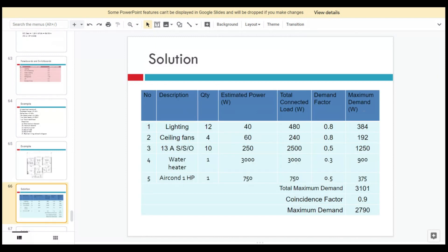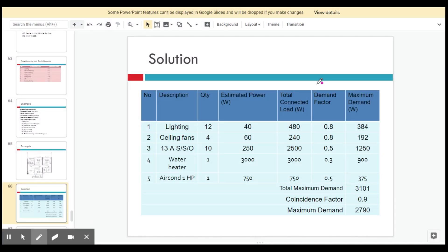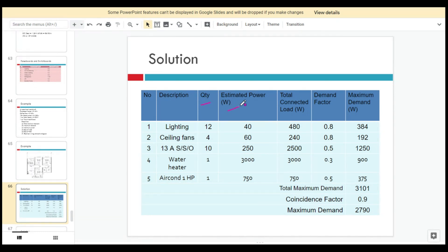From there, with one air conditioner, you have to come up with the load calculation. Load calculation is very important in order to design the electrical system. You put it in table form to make it easier to monitor and calculate the total maximum demand. Write down the description, quantity, estimated power, and total connected load (TCL). TCL is the quantity multiplied by the estimated power.